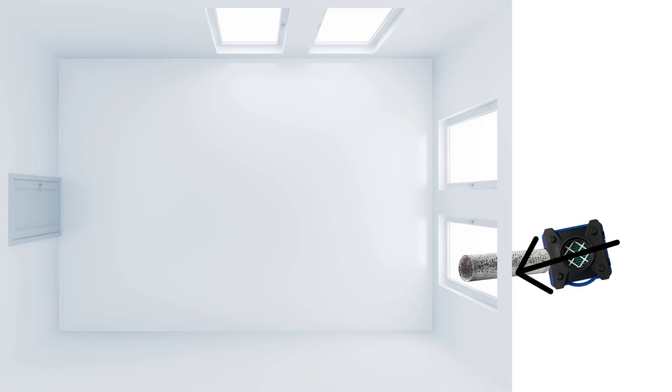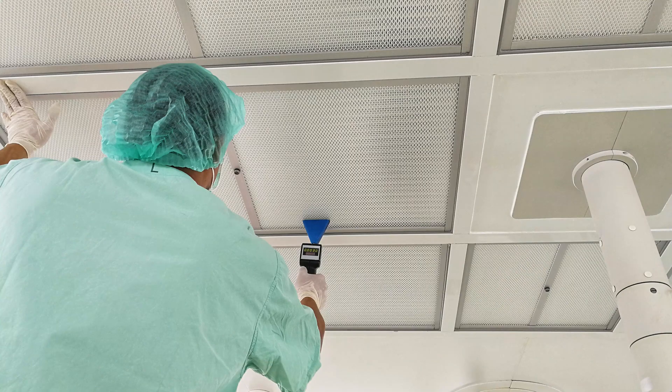Additionally, after a space is verified as clean, you can always place the area under positive pressure by having the unit outside the area and venting back in the clean air. This will help stop any unfiltered air from entering back into the area.